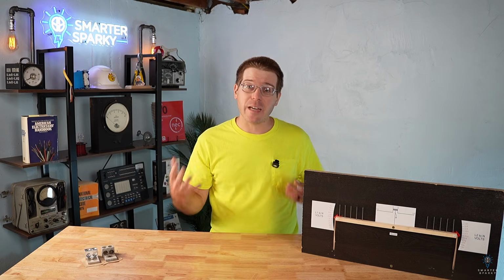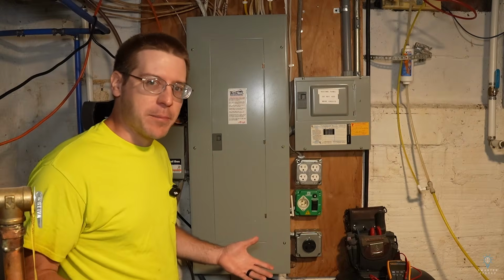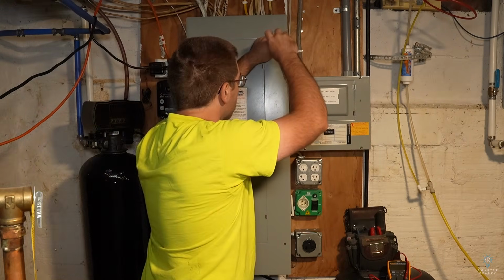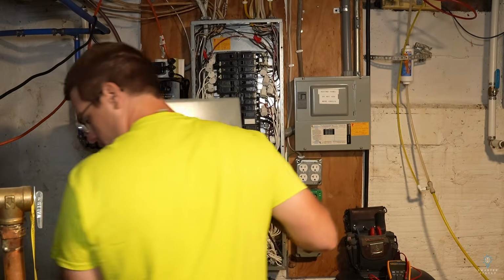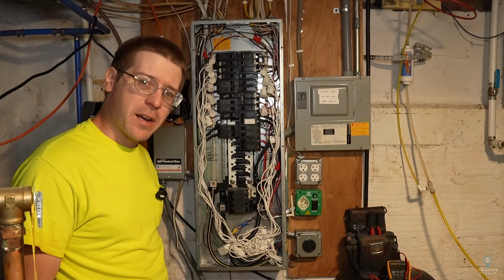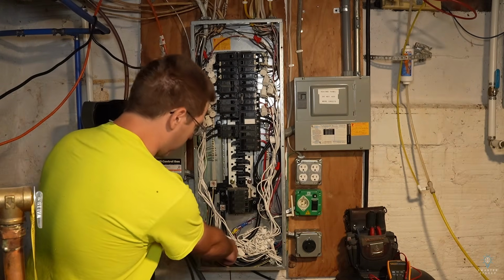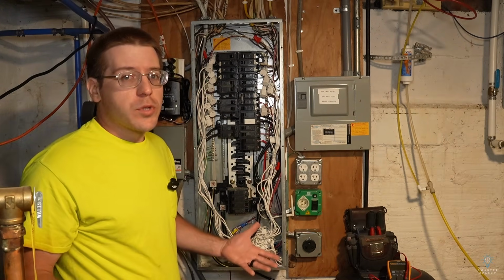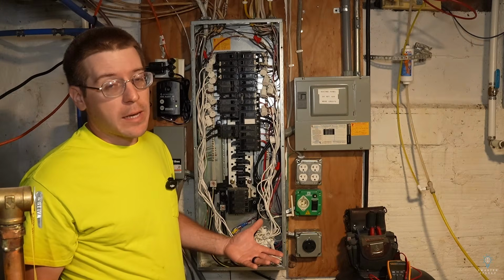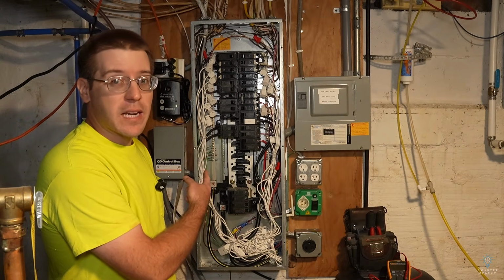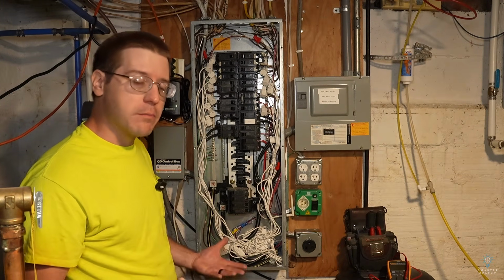Now let's take a look at the actual diagnostics. So the first thing I'm going to do to start really troubleshooting this is open up the panel. We need to get some measurements inside of here. I have a load monitoring system in my panel. That's what all of these extra wires are. Just remember, only qualified persons should do electrical work. It can be pretty dangerous inside of a main electrical panel. If you're not sure, leave it to the pros.